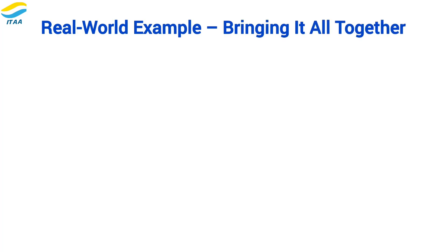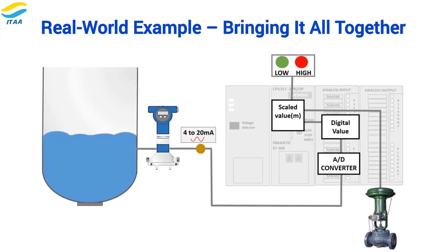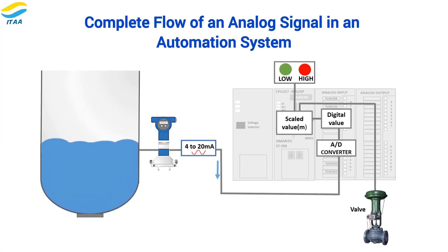Let's put it all together with a quick example. The transmitter in the tank sends a 4 to 20 milliamp signal representing the tank level. The PLC's analog input module reads the signal and converts it into a raw digital value through the ADC. The PLC scales this raw value to an engineering unit like meters so we can read the exact tank level. If the level is too high or too low, the PLC triggers alarms to alert us and keep the system safe. The PLC then sends a control signal via the output card to a valve — our final control element — to adjust the tank level as needed. That's the complete journey of an analog signal in automation, from raw values all the way through to control actions.